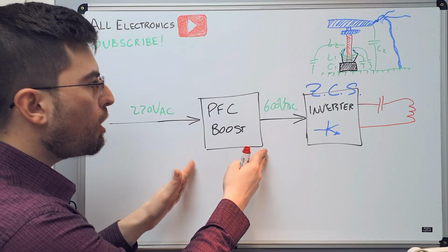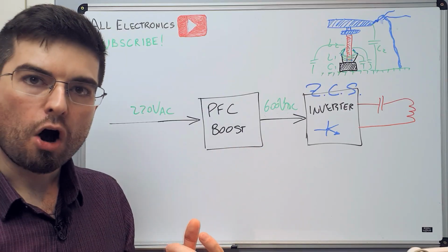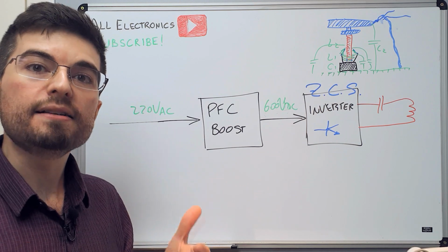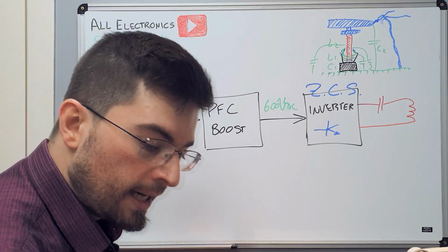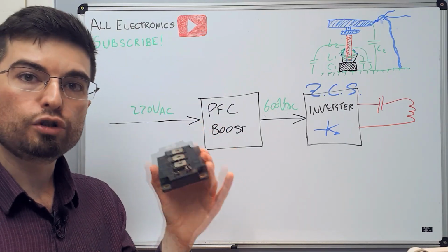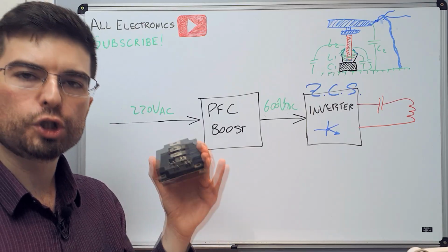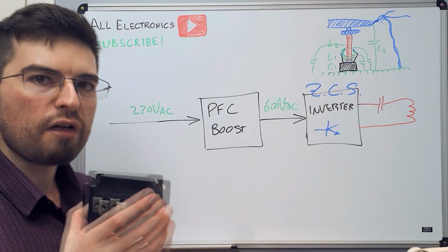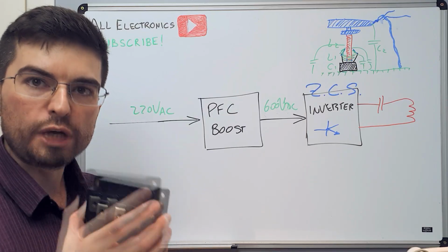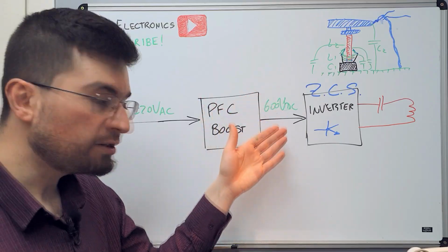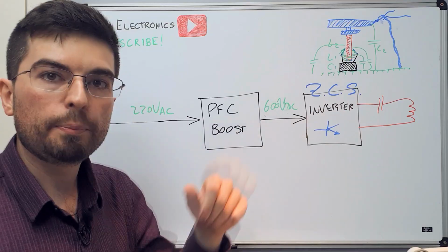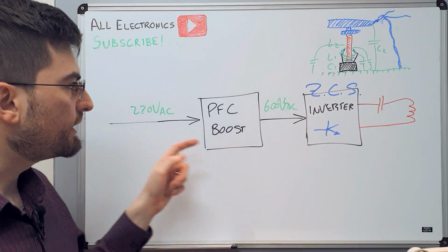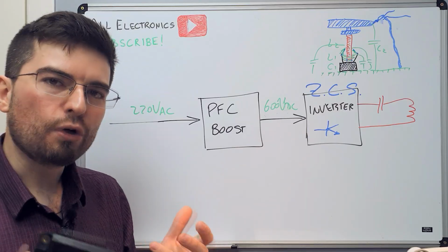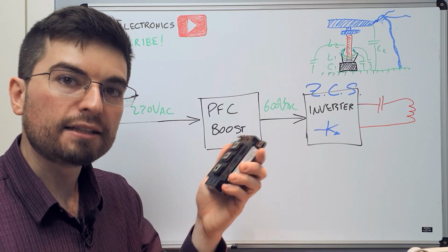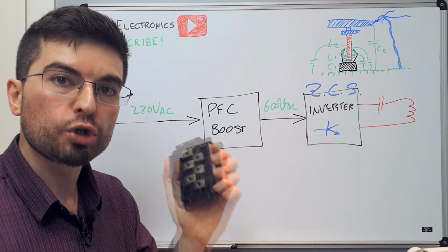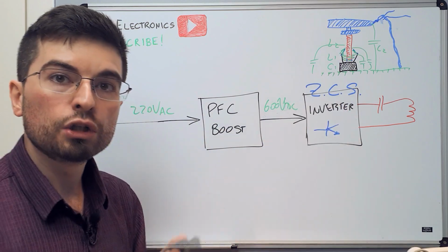But placing one more box here, we have the opportunity to make an even better impedance matching of the energy profiles. These transistors can support 1200 volts, so we have a lot of range. We can make an inverter that switches 600, 800 volts over the primary side. If we directly use a rectifier, we're going to have only 300 volts. So see how we are losing opportunity in the transistor, in the inverter, losing the opportunity of switching more power to the primary side.